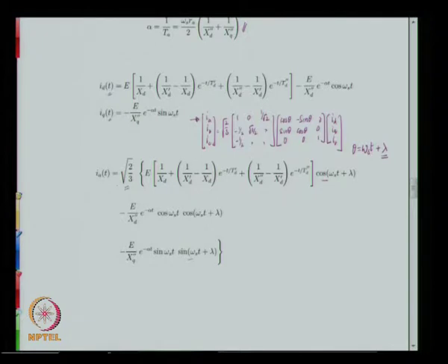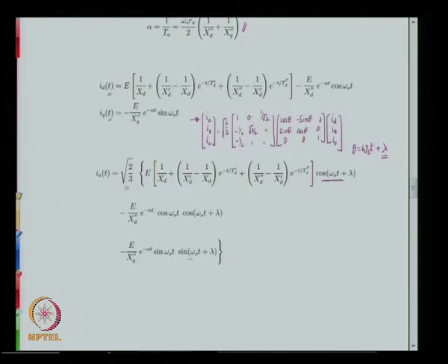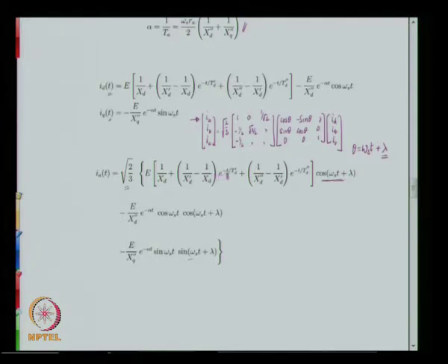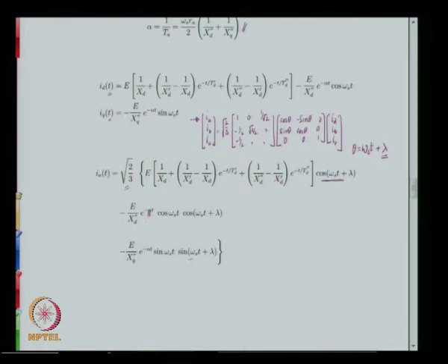Adding up id and iq contributions we get an expression for ia. We see that ia consists of a cosinusoidally varying component whose amplitude is determined by: a constant term e/xd, plus a term that decays exponentially with time constant T'd, another term that decays exponentially with time constant T''d (much faster), and two more terms that decay exponentially with time constant ta — the armature time constant.